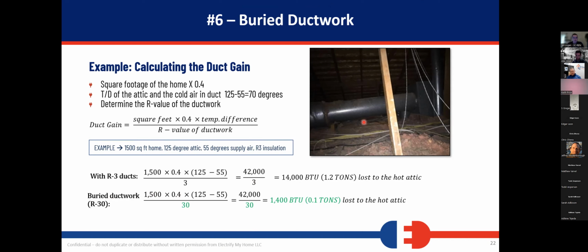So if we can average an R30 on the ductwork, and remember, if a duct is sitting on the surface of the ceiling joists, and we have 17 inches of insulation in the attic, and I've got an 8-inch duct, which is approximately 10 inches around, I've got a good crown of insulation over the top, and really infinite insulation around the sides and down at the bottom. So we can average R30 really easily on ductwork in the attic when we bury it.